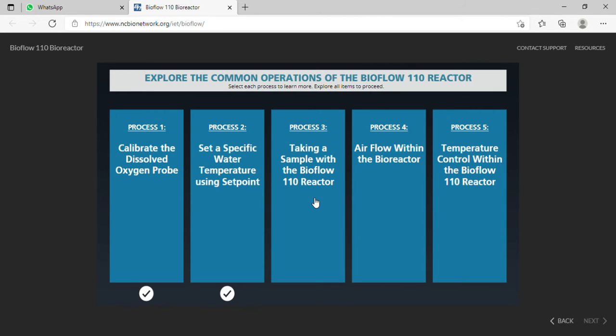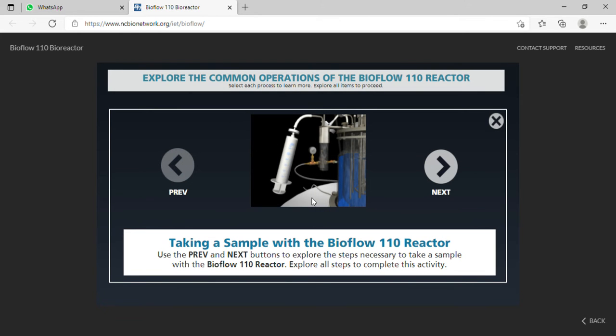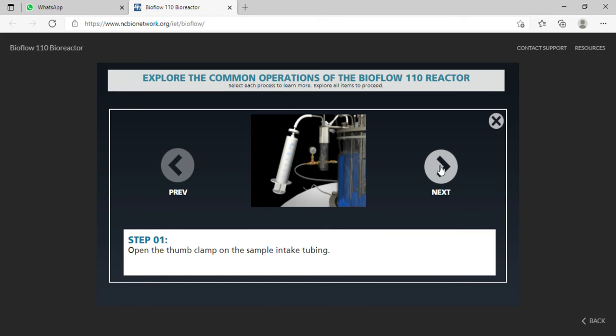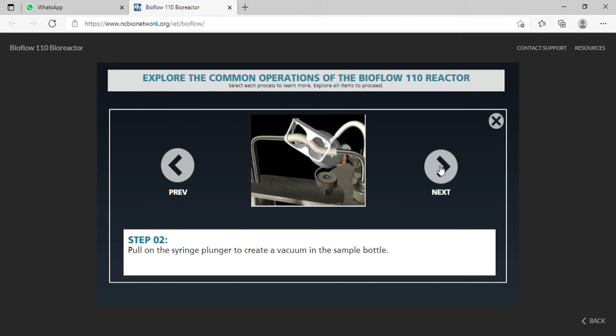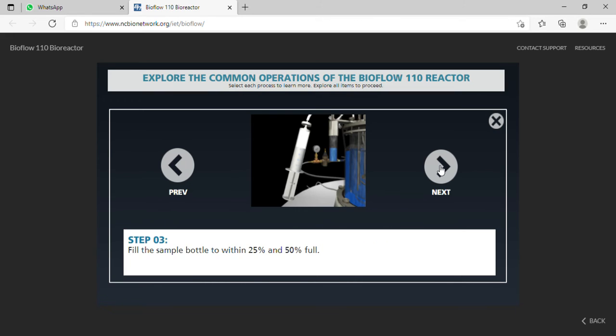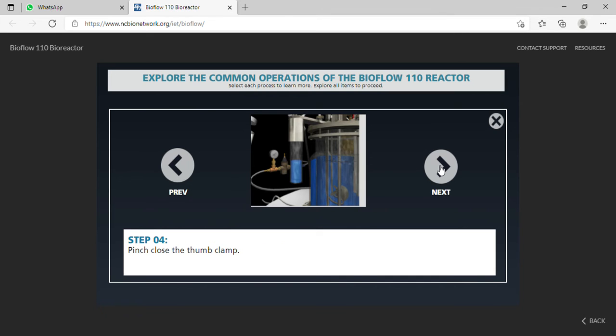The third process is taking a sample with the Bioflow 110 reactor. Step 1. Open the thumb clamp on the sample intake tubing. Step 2 is to pull on the syringe plunger to create a vacuum in the sample bottle. Step 3. Fill the sample bottle to within 25% and 50% full. Step 4. Pinch close the thumb clamp.